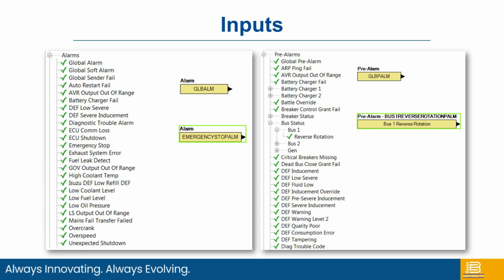Further stuff on inputs, we've got alarms, pre-alarms, and all the different selections that you could ever think of. You can even see some here. We've got DEF, which is diesel exhaust fluid, so that's getting read over the CAN bus. So depending on how the DGC-HD is set up, what it's set up to communicate with and monitor, these options show up to be able to use those in the logic.